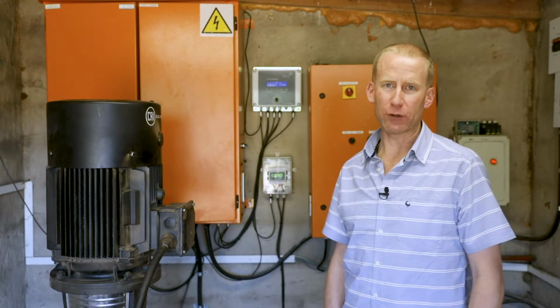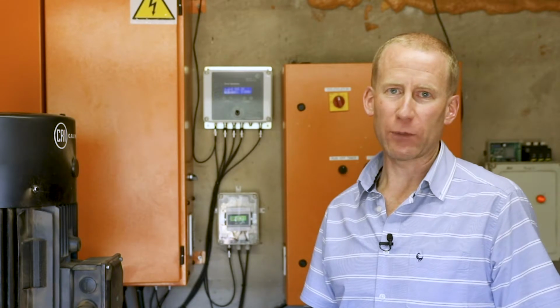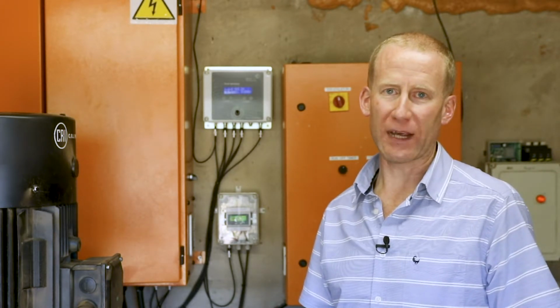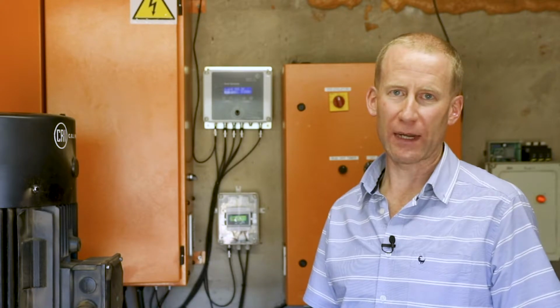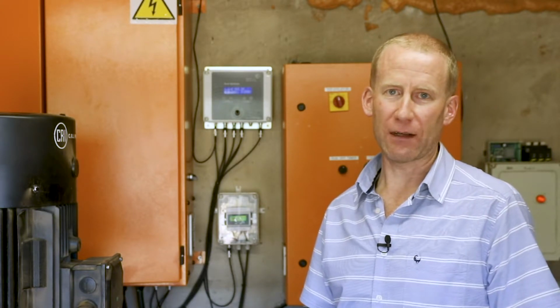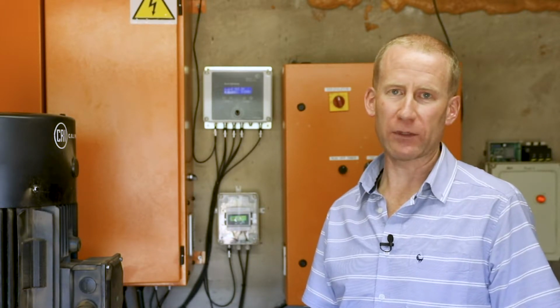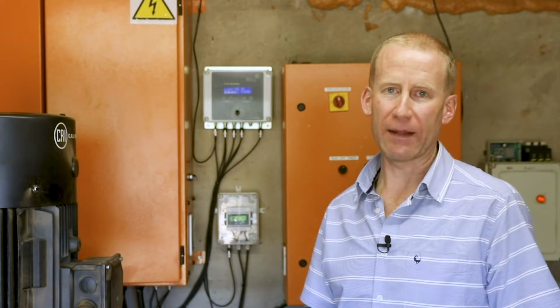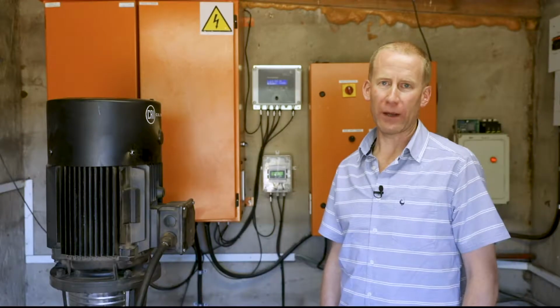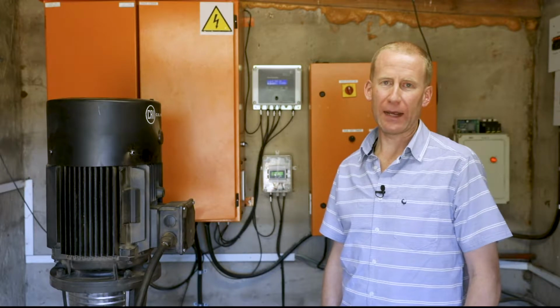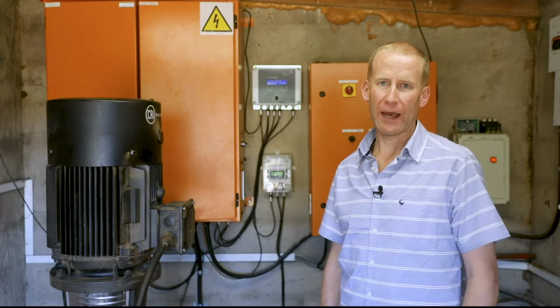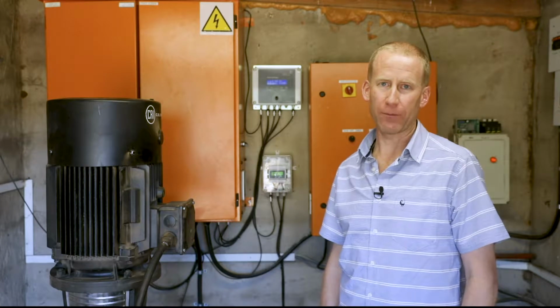If the pump inlet pressure drops too low, then the pump differential pressure drops and the efficiency of the pump is reduced. If the pump inlet pressure drops further, then the pump starts to cavitate and permanent damage is done to the pump. Cavitation sounds as if the pump is pumping small stones. In reality, this is vapor bubbles that form from the very low pressure and then implode against the impeller. When the vapor bubbles implode against the impeller, it erodes away small amounts of metal and permanent damage is done to the impeller. The impeller ends up with a large number of holes in it.